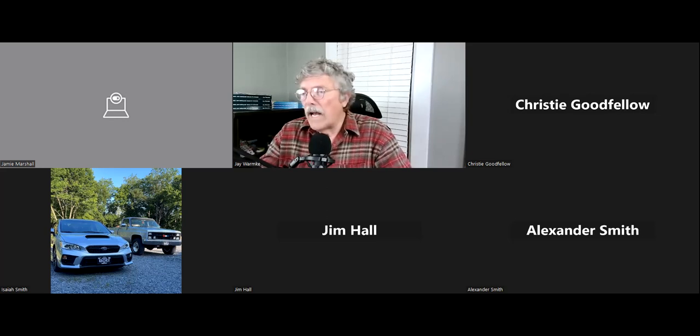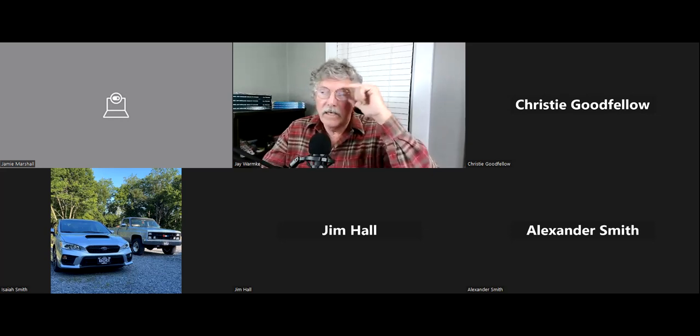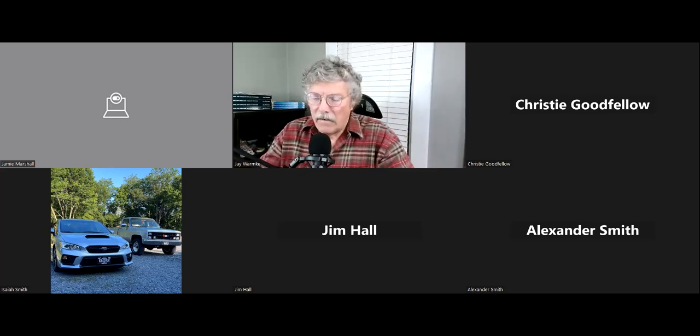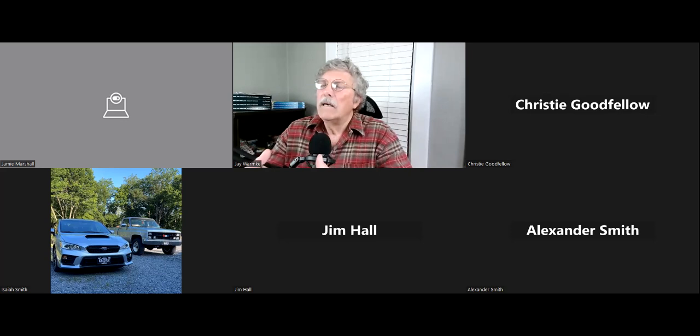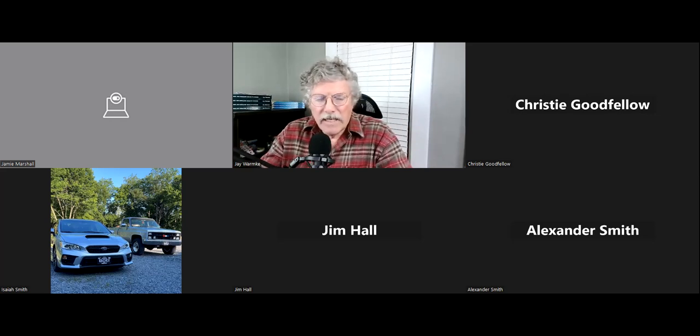Those are going to be the outside boxes. That's typically what we use. You'll just want to make sure it's NEMA 3 or NEMA 4 rated for exterior components. Then there's also things like clear working space for all of these cabinets, boxes, switches, things like that.